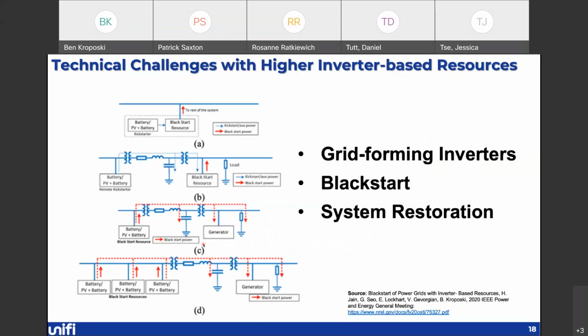In addition to that, when you think about if we move to a system that was 100% inverter based, you also have to design the fact that these systems have to be able to recover from an outage condition. So some of your inverters need to have some grid forming capability to restart the grid, and we typically call that a black start. We've been investigating how you use inverter-based resources to black start systems, but there are challenges with that. For example, when you black start a grid, you have to re-energize transmission lines and transformers, and so you need to make sure that your devices would have that capability to actually re-energize those pieces of equipment. The entire process of restarting the grid is called system restoration, and building all these devices and having them adequately planned to work together to restart the larger grid is an important part of thinking of how to operate a system with that much inverters.